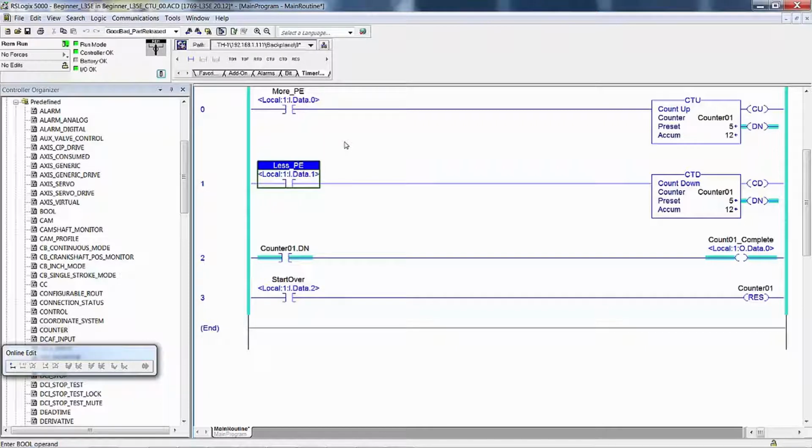With the timer data type, when it's done, it's done. It's not going to go any further. It's not going to count any more units of time under any kind of normal circumstances. However, with the counter, it just keeps on counting up until you hit, what was it, 2 billion and something. The done bit is on anytime the preset is equal to the accumulate or more, or greater. The preset is equal to or greater than the accumulate, then the done bit will be on.